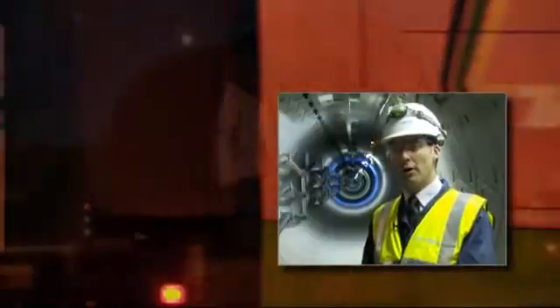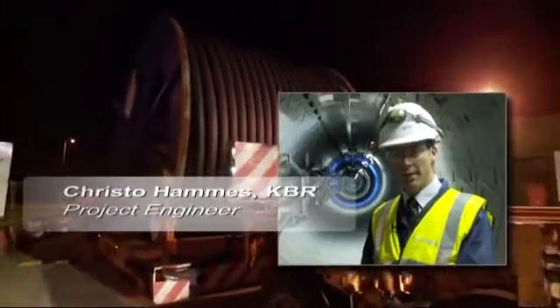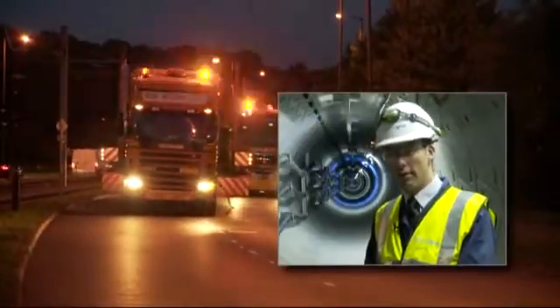The length of the cable is primarily dictated by the weight and the sheer size of the drums. These particular ones are 1150 metres and at 400 kV that's about the biggest that we can safely transport across the London road infrastructure.